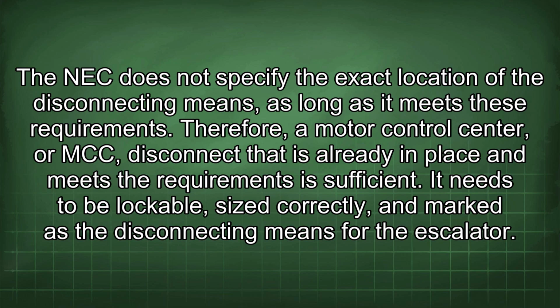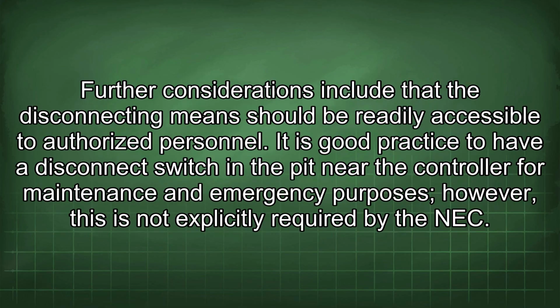Therefore, a motor control center, or MCC, disconnect that is already in place and meets the requirements is sufficient. It needs to be lockable, sized correctly, and marked as the disconnecting means for the escalator. Further considerations include that the disconnecting means should be readily accessible to authorized personnel. It is good practice to have a disconnect switch in the pit near the controller for maintenance and emergency purposes. However, this is not explicitly required by the NEC.